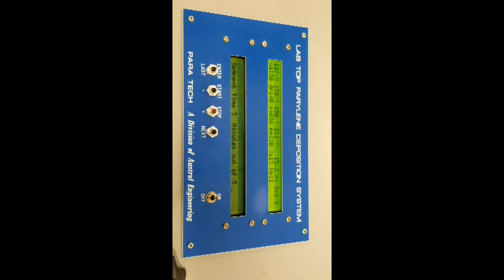All right, we're back. We're 3 minutes into the 5-minute segment 8 of the soak at the 130 degrees for the vaporizer. Typically, you would be seeing an increase in pressure due to the dimer evaporating. So what I'm going to do is simulate that by opening the vent valve real quick, and you'll see the pressure rise, and then when it does eventually fall below the 21, the recipe will end. It'll take a few minutes to pump out. So I'll go ahead and do that now, and you'll see the pressure increase.